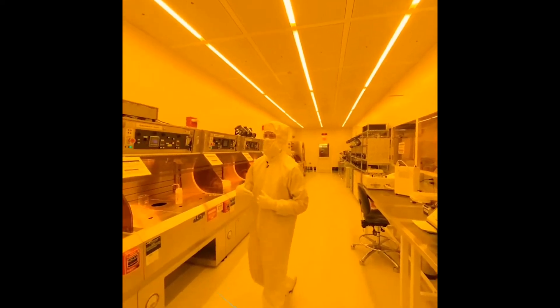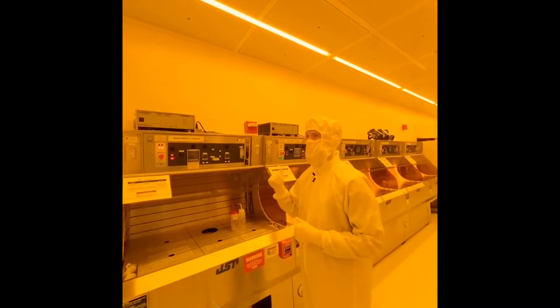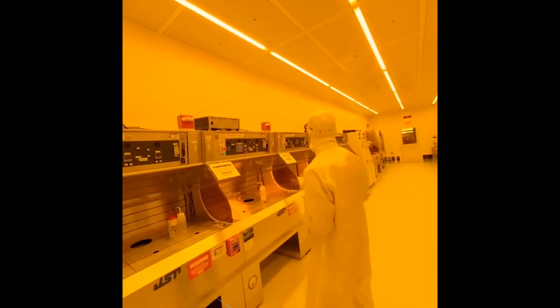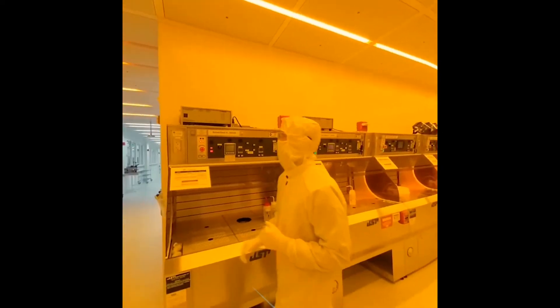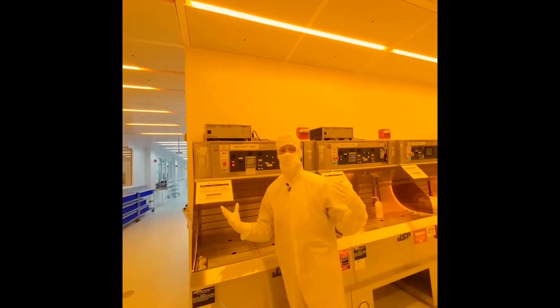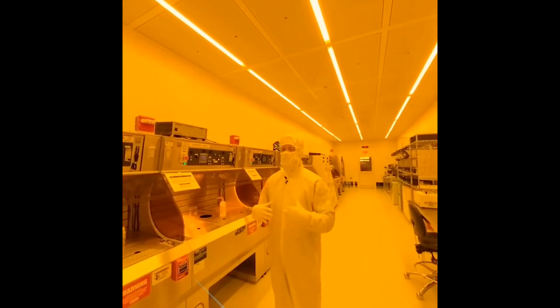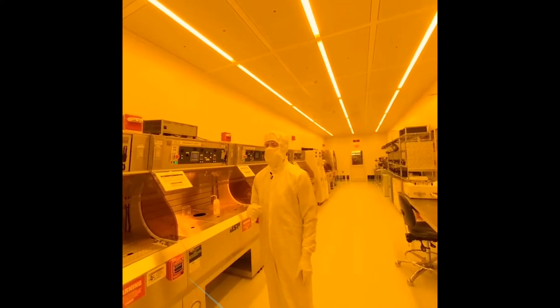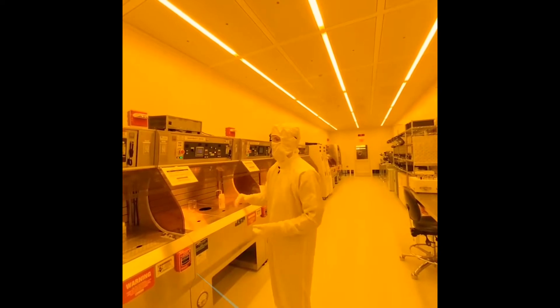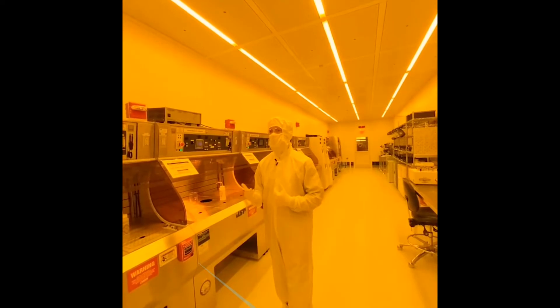At this point, if I was a user, I would want to either find a staff member in the lab or use one of the lab phones and notify them immediately of what's going on. Notice, however, that the other decks aren't off, and our fire alarms and hazardous gas alarms — which correspond to lab-wide evacuations — are also not triggered. So this type of alarm does not require an evacuation from the lab. However, you will want to notify staff as soon as possible. You also don't want to work at a bench or a tool that is down like this, because those safety features and interlocks might not be functioning properly.